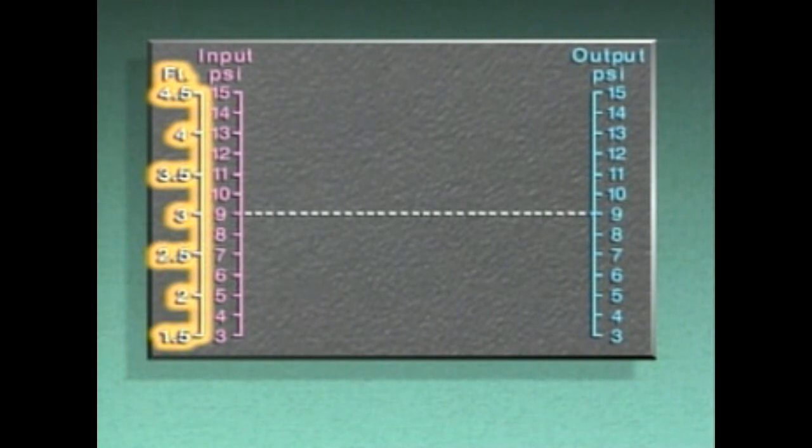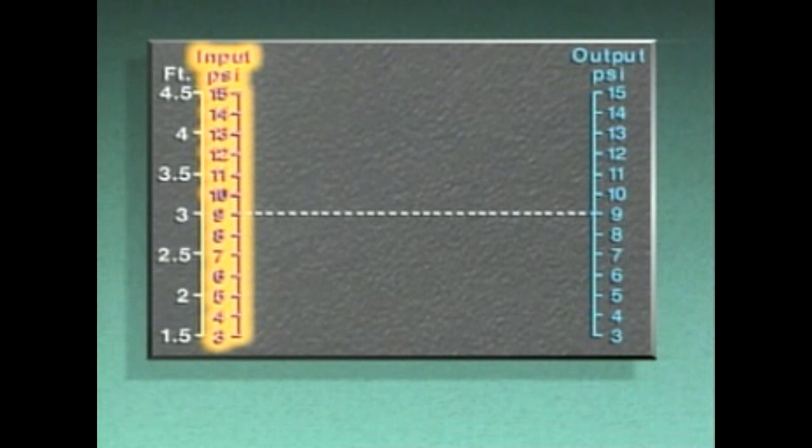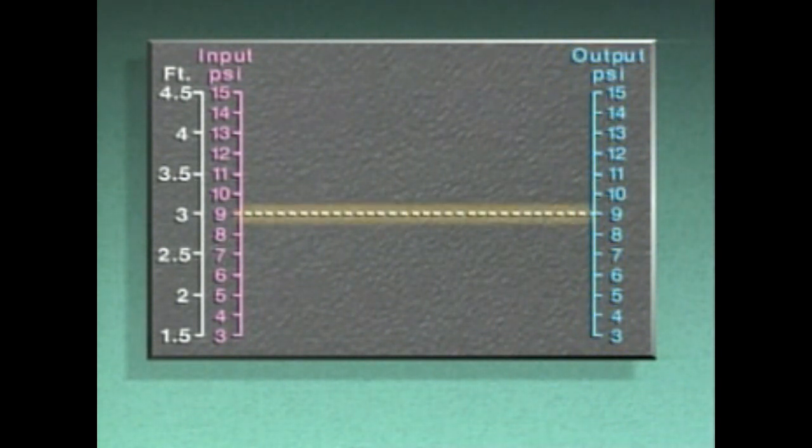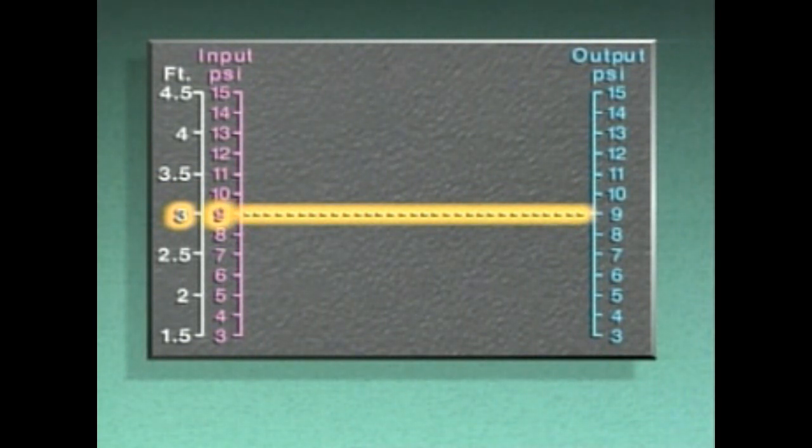On the graph, the scale on the far left is marked off in feet to indicate the water level in the tank. The next scale indicates the value of the input signal to the controller in pounds per square inch, or PSI. The scale on the right indicates the value of the output signal from the controller, also in PSI. The dashed horizontal line represents the set point for the water level. In this example, the set point is three feet, equivalent to a 9 PSI input signal and a 9 PSI output signal from the controller.